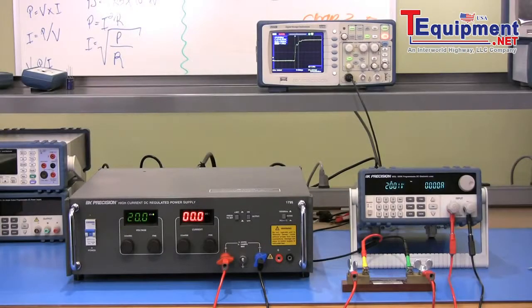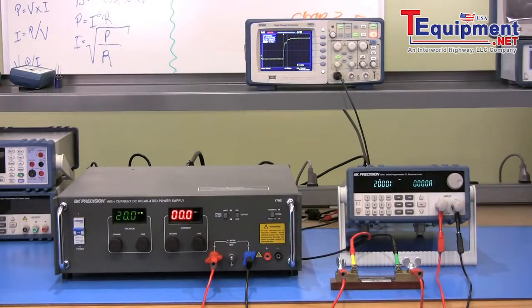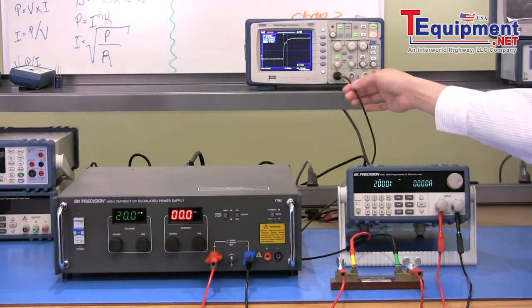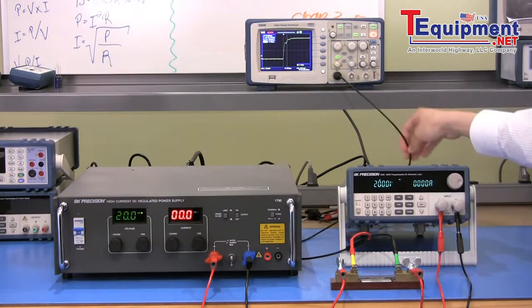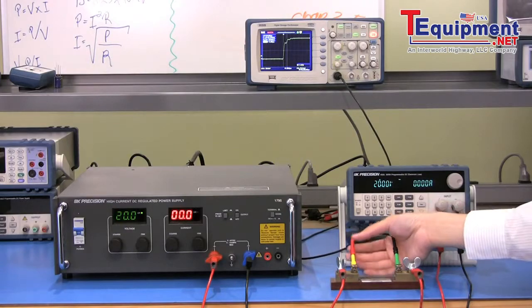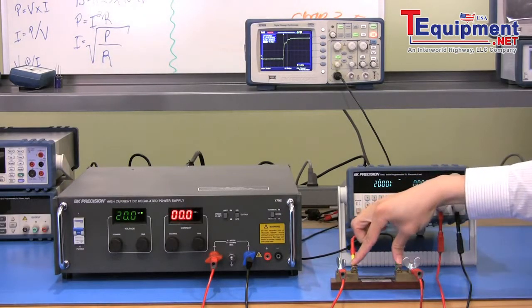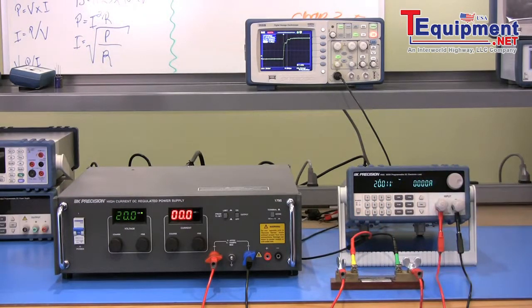For demonstration, I have a setup here to measure slew rate of a BK Precision 8502 DC electronic load. Here, I have a BNC to banana plugs cable connected to a DSO, with the banana plugs connected to a shunt resistor rated for approximately 66 milli-ohms, 15 amps.